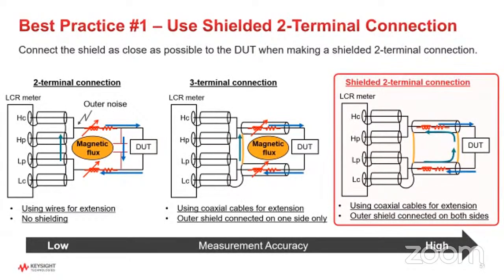The three-terminal connection shown in the center only connects the outer shield surrounding the extension cables on one side, and that's better, but it's still going to give you problems because there's not a complete return path for any currents that are generated in those outer shields.